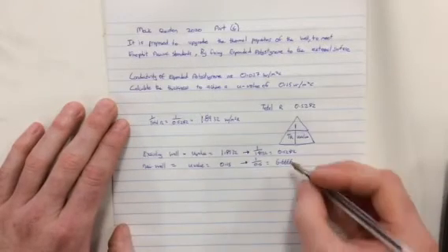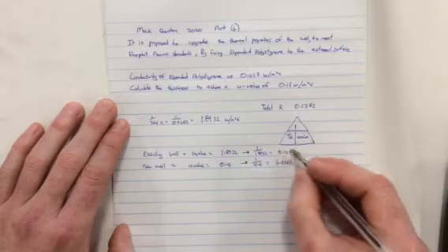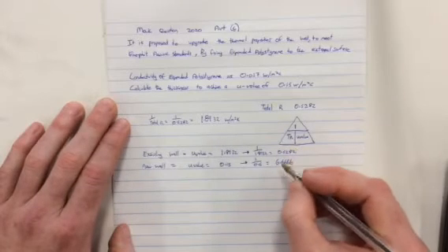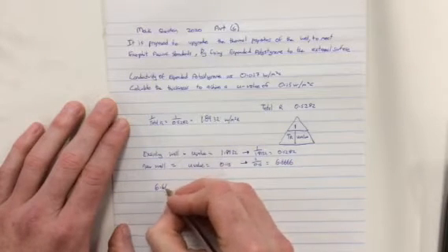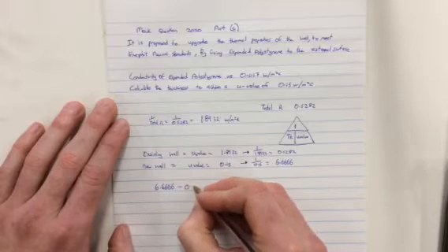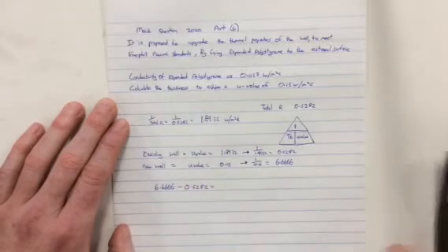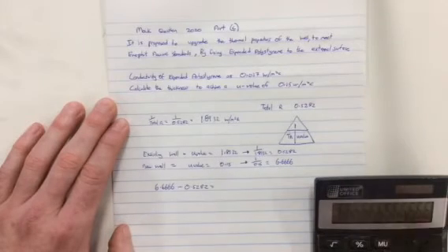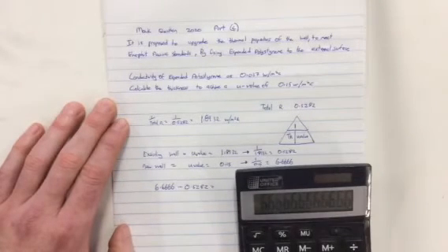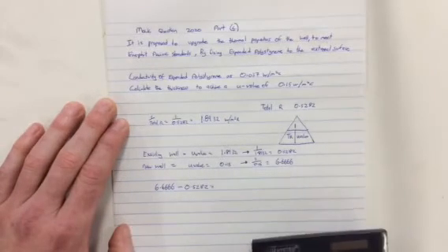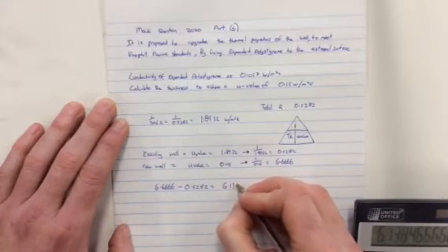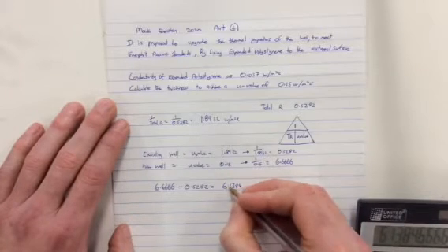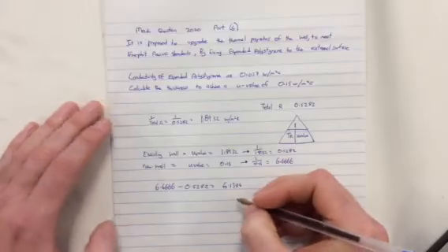So that's the resistance total we're required to have. That's what we have so far on our wall, and we're trying to get it up to that value. So we need to find the difference. 6.6666 minus 0.5282 will give us the value of the resistance that we need to find, which is 6.1384. So that's the resistance of the insulation that we're required to have.